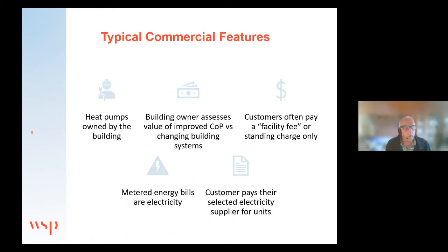That means the building owner can, on an individual basis, assess whether it's worth improving the coefficient of performance of that heat pump, or by changing the building systems to reduce flow temperatures. Most buildings, in terms of a retrofit, would be designed with relatively high flow temperatures, and that would have an impact on the heat pump performance and therefore the life cost of that system. So the building owner can look at that on their own merits and take into account their own considerations when looking at the relative value of those investments.